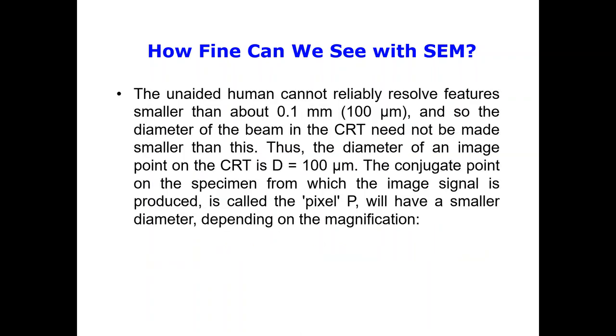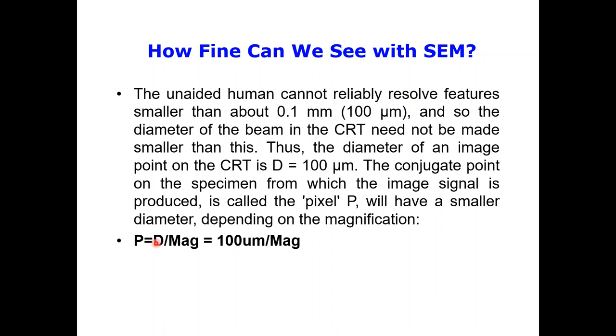The unaided human eye cannot reliably resolve features smaller than about 0.1 millimeters. So the diameter of the beam on the CRT need not be made smaller than this — the diameter of the image point on the CRT equals 100 microns. The conjugate point on the specimen from which the image signal is produced is called the pixel, denoted P, which has a smaller diameter depending upon the magnification. The relation is: P = D / M, where D is the CRT diameter (100 microns) and M is the magnification.